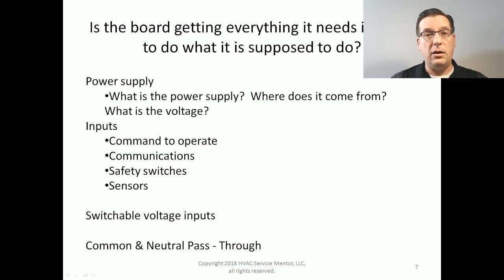And he had called me up on the phone and was saying, hey, I think I've got a bad control board here. I said, okay, great. How do you know it's bad? What do you think is wrong with it? Because we're working together on this. And he says, well, I've got voltage at the control board, but it's not working. Cool. What voltage do you have? And he said, I have 120 volts. I said, great. However, that's not the voltage that makes the board work. The board runs on 24 volts. So that is important. You need to know what voltage the board works on.